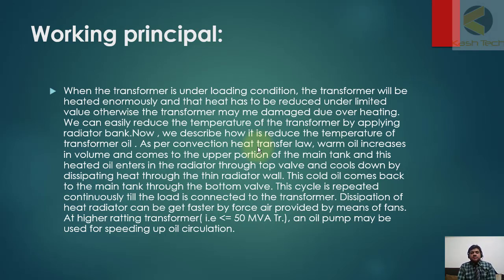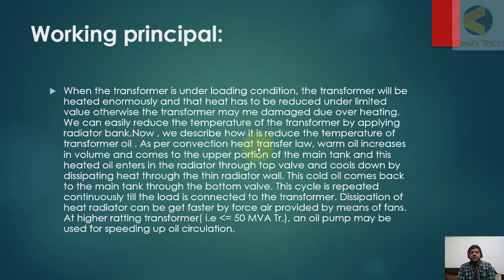Now we describe how it reduces the temperature of transformer oil. As per the convection heat transfer law, warm oil increases in volume and rises to the upper portion of the main tank. This heated oil enters the radiators through the top valve and cools down by dissipating heat through the thin radiator wall. The cold oil then comes back to the main tank through the bottom valve.